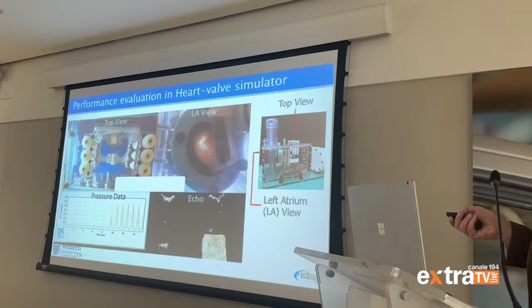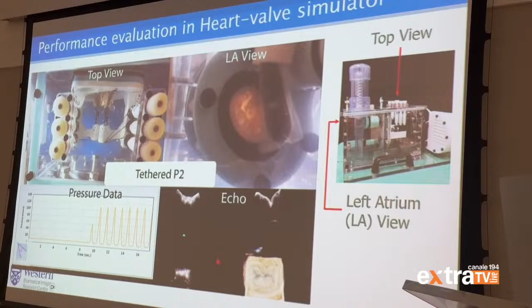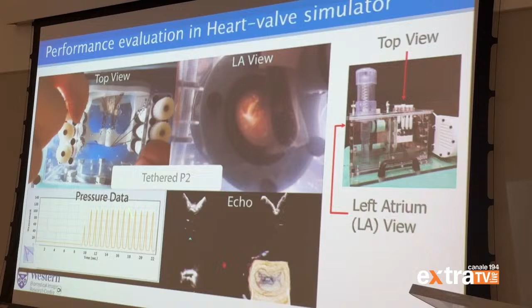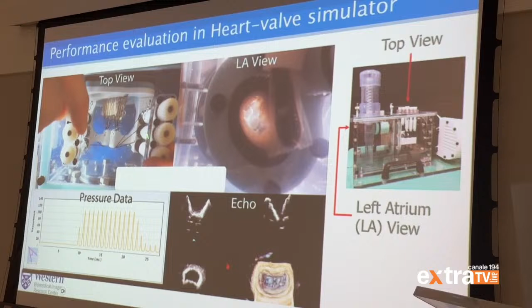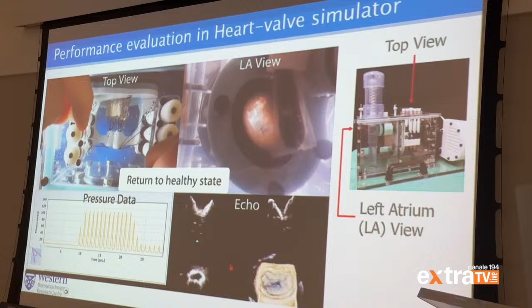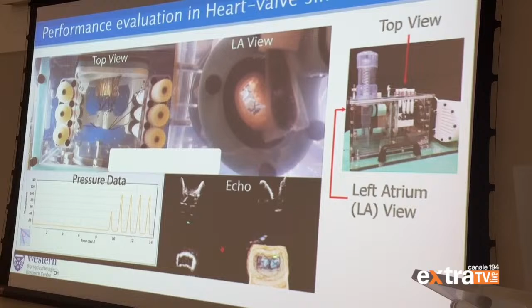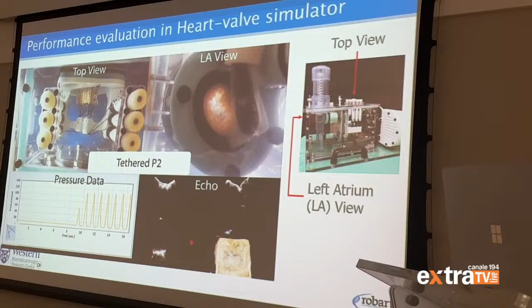Then we can put this into the device that John showed earlier and start to do surgical repair and validation on this. Here's what the simulator looks like from various views. We have a camera in the simulator that can show us exactly what's going on with the valve. We've got pressure sensors that can show us the different pressures as we change the dynamics of the flow by changing the tension in these cords. And we can also look at the three-dimensional transesophageal echo, the three-dimensional ultrasound. So we've done a very good job of replacing the need for live animal studies. And we literally haven't done an animal study in 15 years now since we've had this technology available to us.